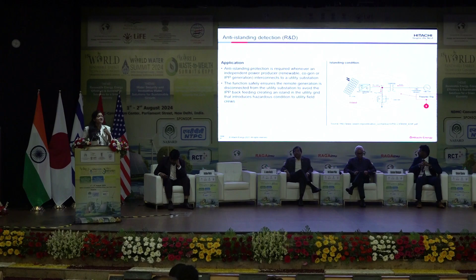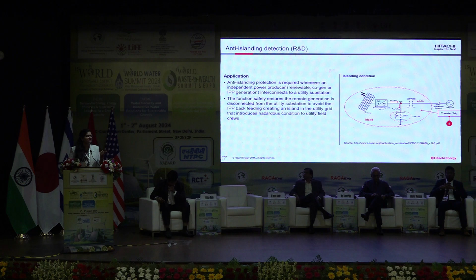So that's where we try to calculate the equivalent Thevenin impedance, to see what kind of jump the system would see in terms of impedance. The network could have different generation sources, distribution, loads connected, so it's dynamic - there's no one setting which could work. So how does that ratio look like, and what's a good ratio to enter into our islanding algorithms?